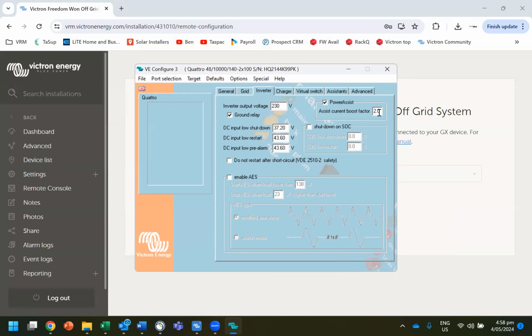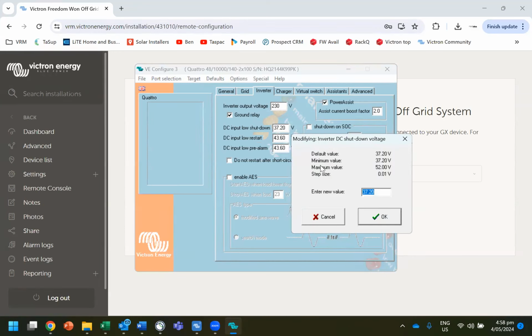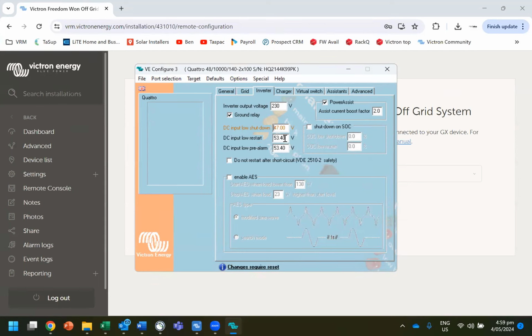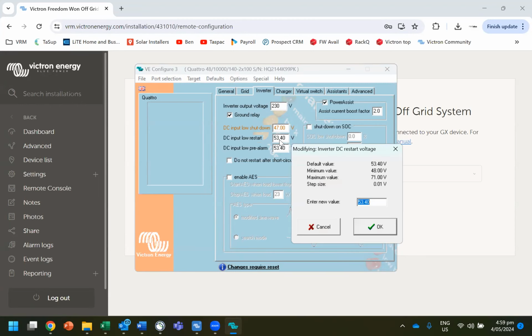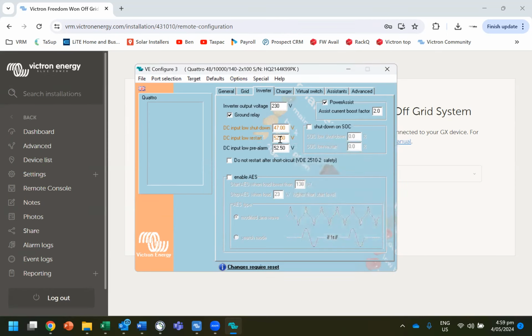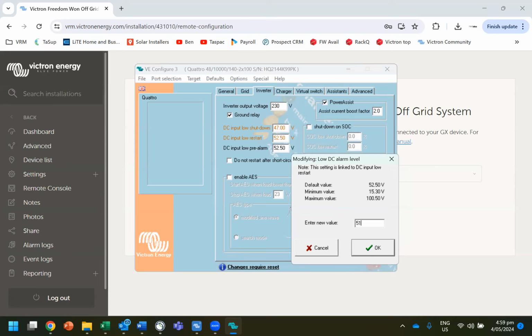Power assist basically means if the load is likely to be above the generator level, then the inverter will assist the generator with high peak loads. Now we want to change the DC shutdown. This is going back to that Freedom Won setup page on the Victron website, and the voltage there is 47 volts. And then the low voltage restart: it'll turn off at 47 volts and it will wait until it's up to 52.5 volts before it restarts. And then the alarm is 51.5.